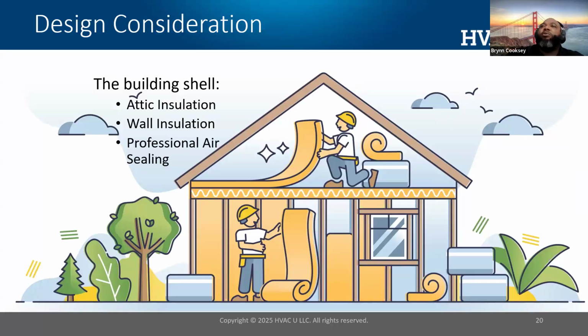Now, before you dive into a heat pump project, you should really think about whether you should weatherize your building shell. Some people call this permanent load reduction. They'll say, hey, I want to put a heat pump in, but I want to put in a smaller heat pump, maybe one that doesn't have as much capacity. If I tighten up my building shell by adding insulation, such as in the attic or walls, or doing air sealing, I'm going to reduce that load. Therefore, I can get a smaller heat pump, better energy savings, and so on. So prior to using heat pump technology, you should ask yourself the question: should I weatherize prior to going all electric?